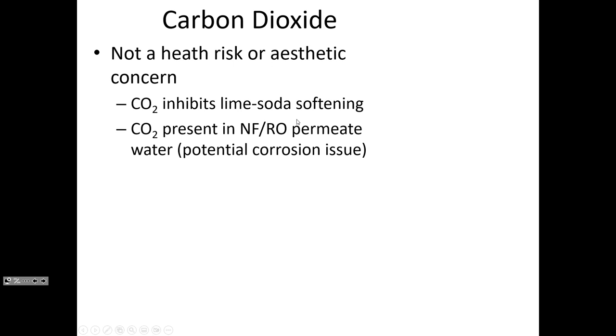CO2 can also be a post-treatment concern with nanofiltration or reverse osmosis, because those processes remove constituents like alkalinity. Dissolved gases like CO2 pass through nanofiltration or reverse osmosis, so the previous buffering capacity — the quantitative capacity to neutralize an acid — is filtered out while CO2 passes through. CO2 dissolved in water dissociates into carbonic acid, H2CO3, reducing the pH to about 4, which is acidic enough to cause corrosion in pipes.